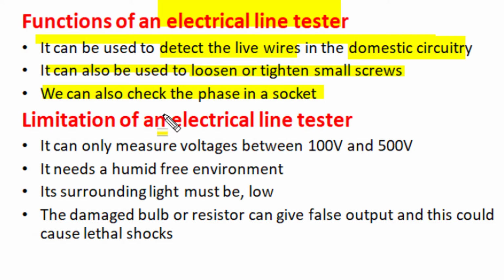Now this electrical line tester has certain limitations in use. It can work only with voltages ranging from 100 volt to 500 volt. For voltages less than 100 volt, the current in the neon bulb circuitry becomes so small that it may not give you clear visible indication, and for test voltages more than 500 volt, the current in the line tester circuit as well as in the human body may create shock conditions. So it is recommended that one should not use an electrical line tester in a high voltage circuit having voltages more than 500 volt.